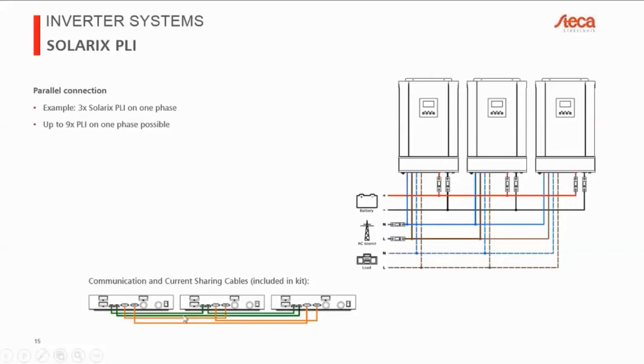So down here, we have a diagram of how to connect the communication and the parallel cables, the current sharing cables. Basically, the orange lines here are the communication cables. So here, this is where we synchronize parameters. This is where, if we have a three-phase system, we do the phase shifting of the phases, 120-degree phase shift. So all of the digital communication happens across those cables.